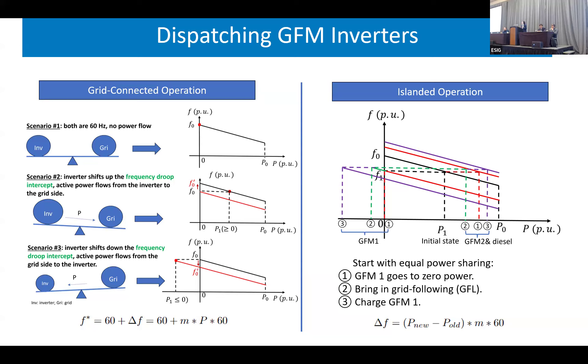For islanding operation, everyone thinks droop is used for power sharing — the old-school approach. But grid-forming in islanding mode can also be dispatched like a grid-following inverter by playing with droop. If you have a target power — say your battery is low and you want to charge — you calculate the delta_f shift based on the dispatch rule. This is very simple and effective for controlling grid-forming inverters in islanding mode to output target power. You can apply this same rule to all inverters to achieve specific target power outputs.